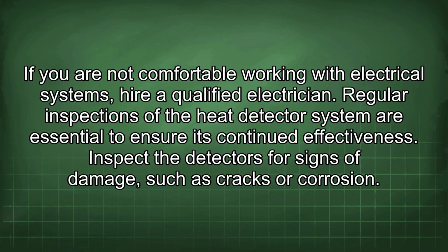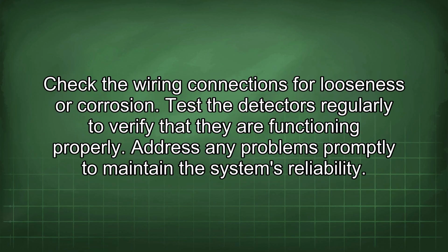Regular inspections of the heat detector system are essential to ensure its continued effectiveness. Inspect the detectors for signs of damage, such as cracks or corrosion. Check the wiring connections for looseness or corrosion. Test the detectors regularly to verify that they are functioning properly. Address any problems promptly to maintain the system's reliability.